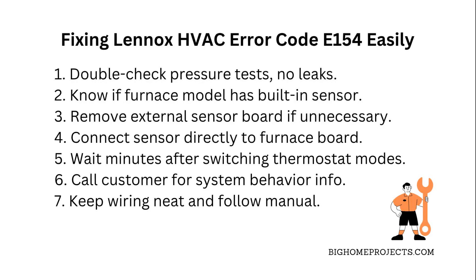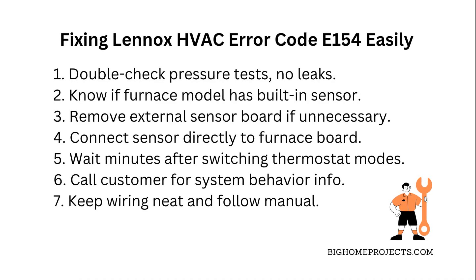If you accidentally install an external board and hook the sensor to it, the system throws that error. The fix? Remove the external board and connect the sensor directly to the furnace board like it's supposed to be.